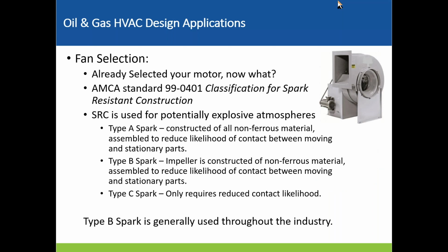Selected our motor. Now we have different spark resistant construction types for different fans. A type A spark is constructed of all non-ferrous materials, kind of the safest option. Also not a very common one, and an expensive approach. Type B spark is where the impeller is constructed of a non-ferrous material and is assembled to reduce likelihood of contact between moving and stationary parts. And type C spark just requires us to reduce contact likelihood. I've generally seen type B spark used throughout the industry. Definitely something to be aware of as we're selecting these fans.